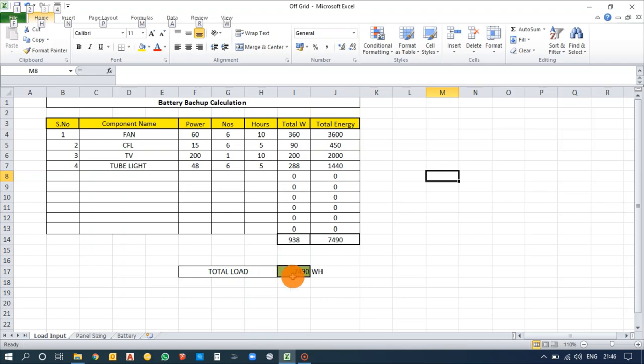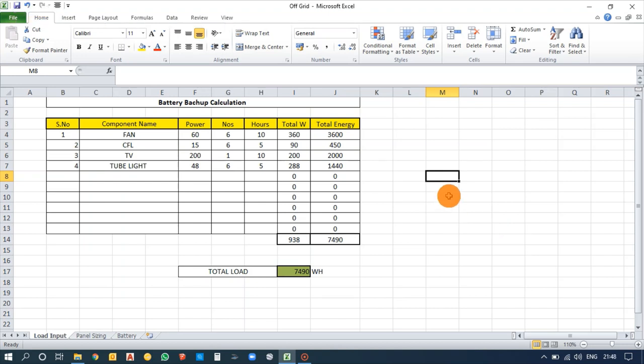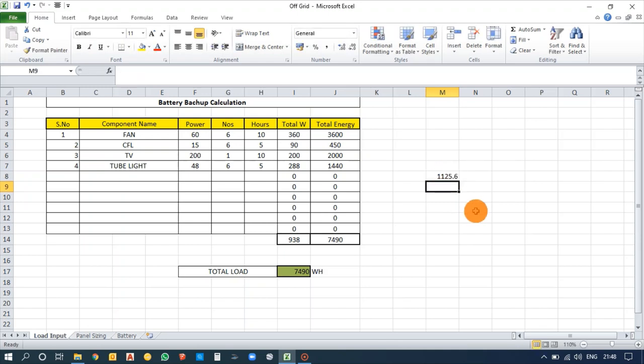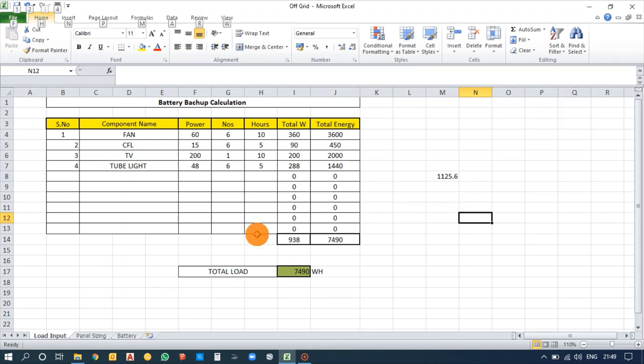After calculating the total load, you need to select an inverter. Inverters are rated in kVA. The calculation is 938 watts × 1.2, giving 1,125 watts — so you can select a 1.5 kVA inverter in this case. Now, moving on to panel sizing.